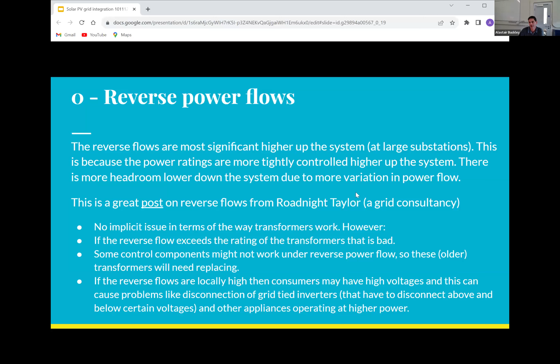This is an example of reverse power flows in reality at one of the largest substations on the Great Britain network down in Cornwall, the Indian Queens substation. We see that as the PV output increases through that substation, and this is modeled data from the PV Live service that we deliver, the demand measured through the substation reduces below zero. And we have these high reverse power flows through that substation. There are several other grid supply points where there are also reverse power flows.